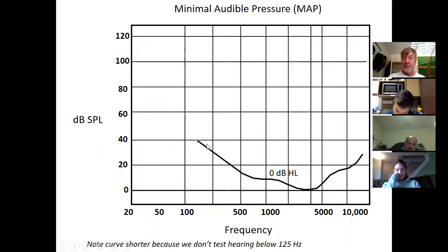And 2,000 hertz is actually about 0 dB SPL. 500 hertz is actually about 12 or 15 dB SPL. 125 hertz is actually about 40, read it, 40 dB SPL. Look at the line here, 40. I'm not lying, okay?